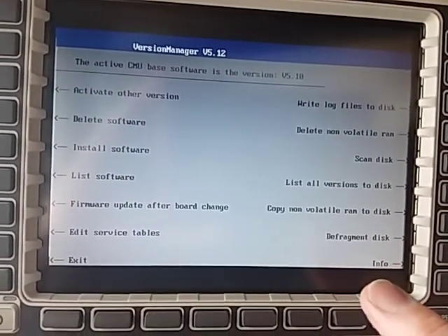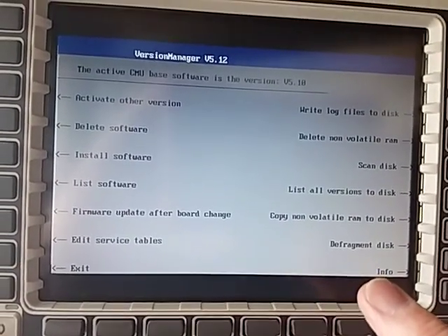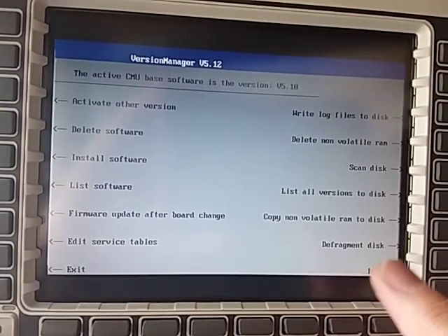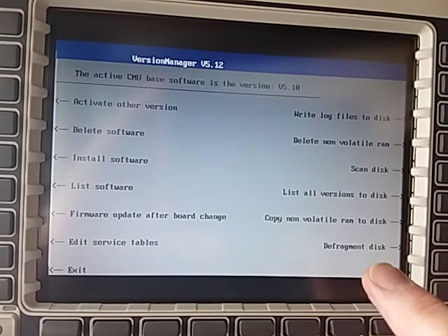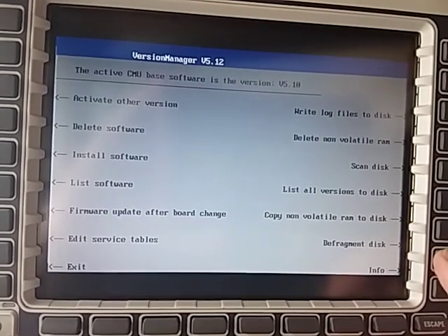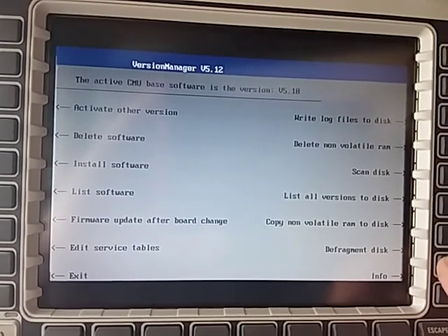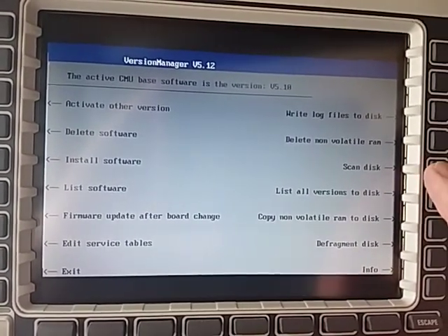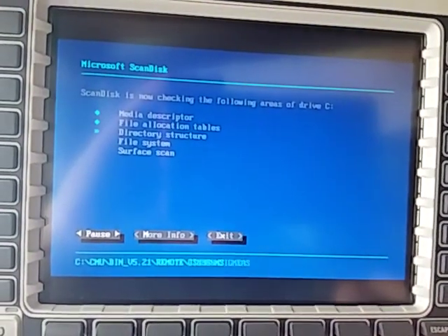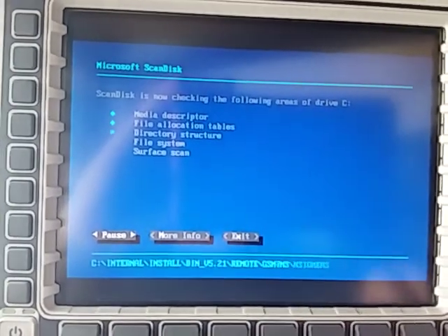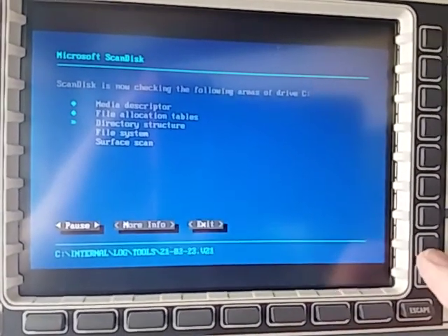the analyzer runs on a DOS system. And so, typical of the older MS-DOS systems, the disk does get fragmented, so it does pay to do a defrag if you've been using it a lot. First of all, you should perform a Scandisk. This does the standard Microsoft Scandisk.